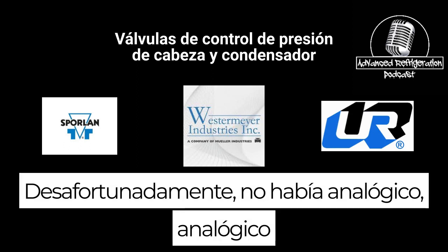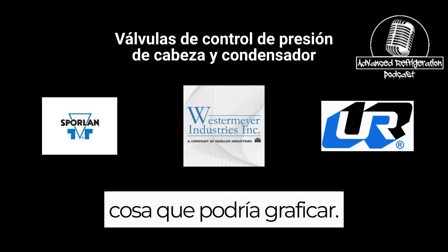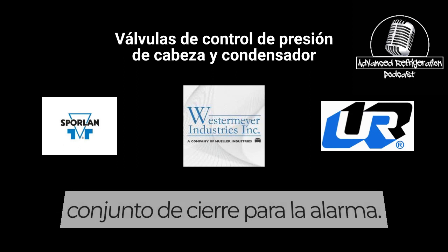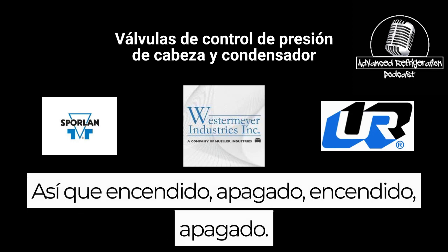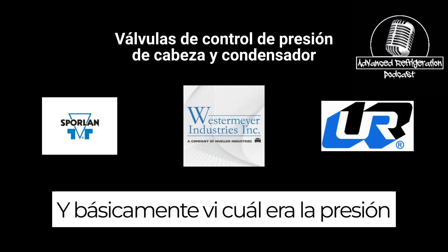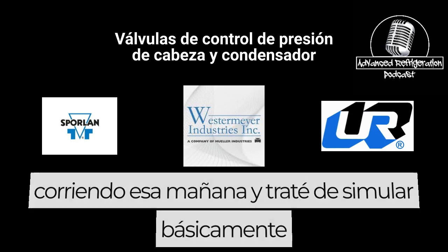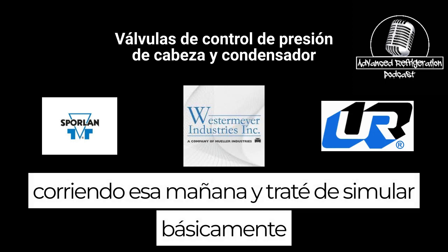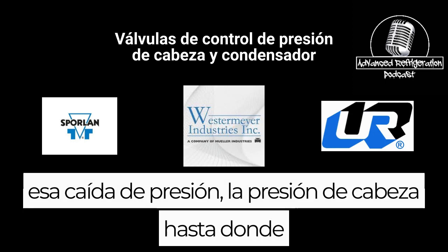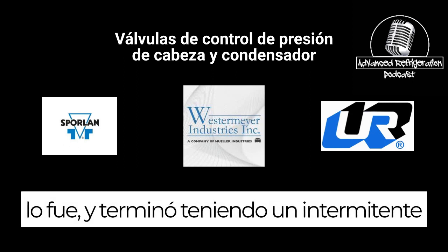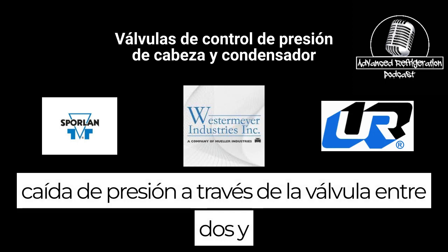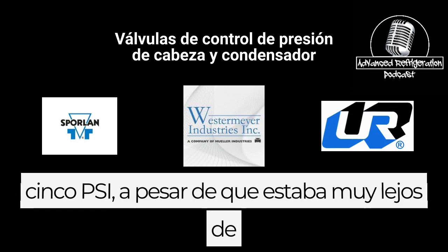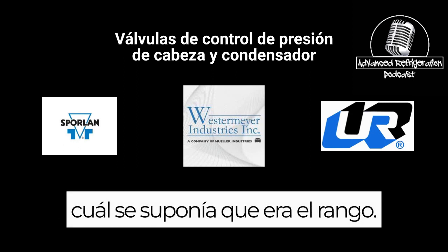Unfortunately, there was no analog thing that I could graph. It basically was just a digital set of closure for the alarm. So on, off, on, off. And basically I just saw what the pressure was running that morning. And I tried to simulate that, basically drop the head pressure down to where it was. And it ended up having an intermittent pressure drop across the valve anywhere from 2 to 5 PSI, even though it was well away from what the range was supposed to be.